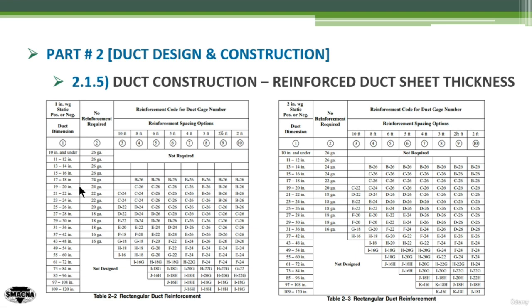However, if the duct size is bigger — let's say 36 by 20 — I can go to 36. This gives me the option: if I don't want to use reinforcement, I can use gauge 18. If I will use reinforcement, this will increase the gauge slightly, given that I need to follow reinforcement class E, or class D in the case of 5-foot spacing, or class C in the case of 2-foot spacing. If I don't want reinforcement, I can go with gauge 18.